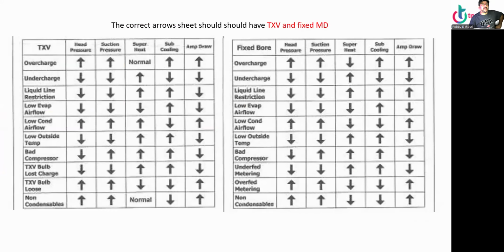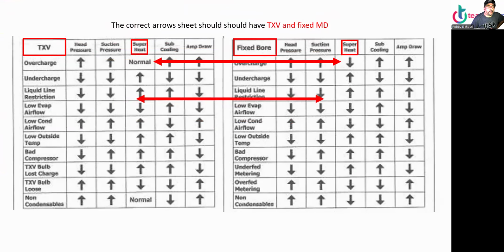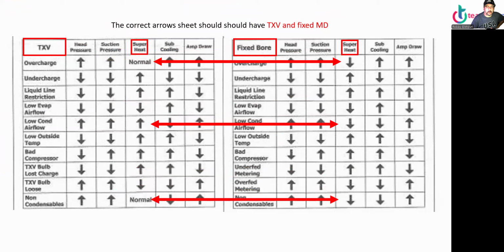All right, so the correct arrow sheet should show both TXV and fixed metering device, fixed bore and TXV, because the superheat changes a little bit. Superheat changes from normal, and here it changes. So you have to be careful when you look at the internet. A lot of things are wrong.